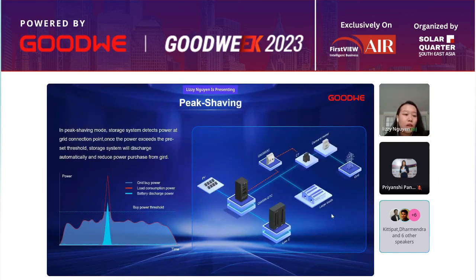Next, our energy storage can help with peak shaving, similar to time of use. The peak shaving mode can detect power at the grid connection point, and you can set a parameter to a certain number. Once the power exceeds that number, the storage system will start to discharge automatically from the battery and reduce the power purchased from the grid.